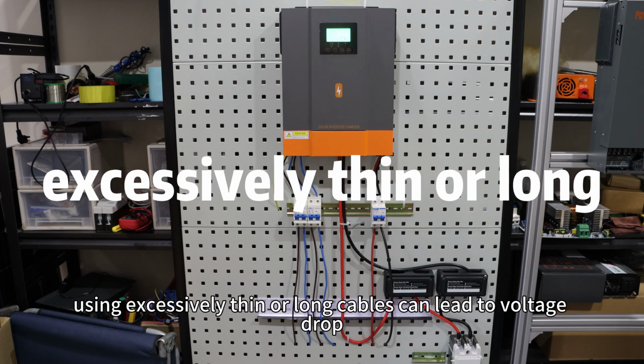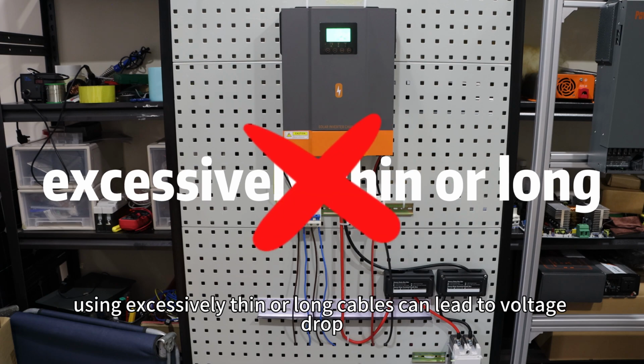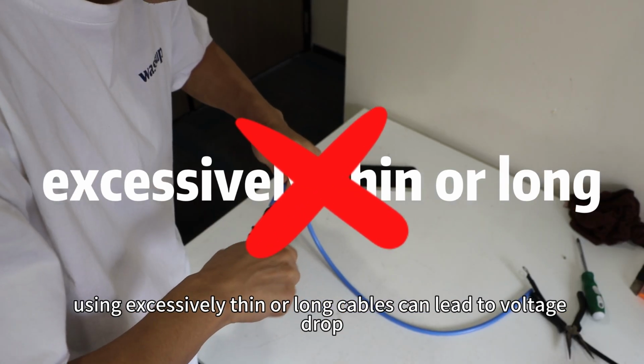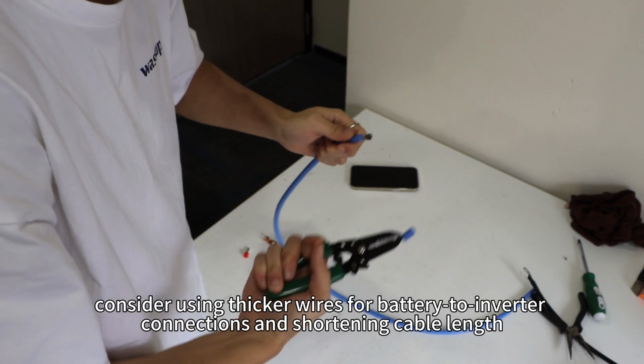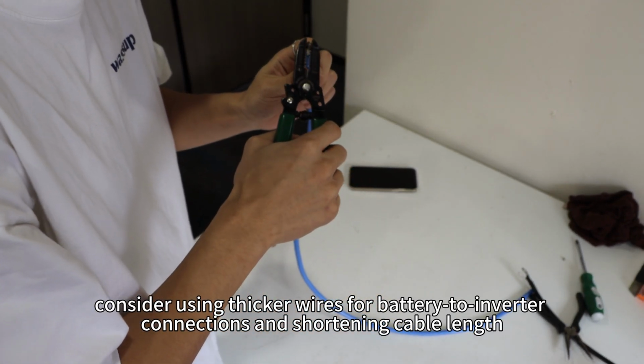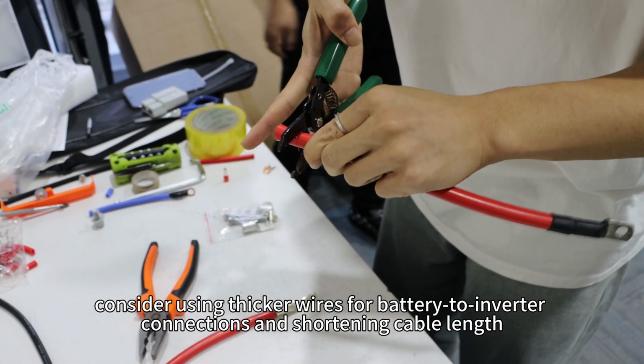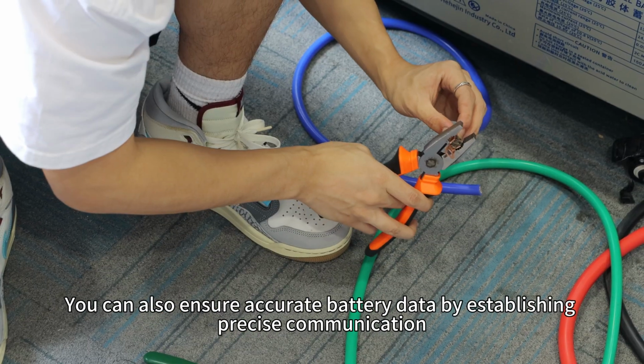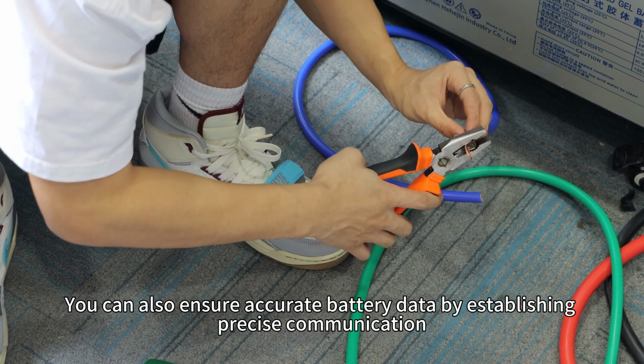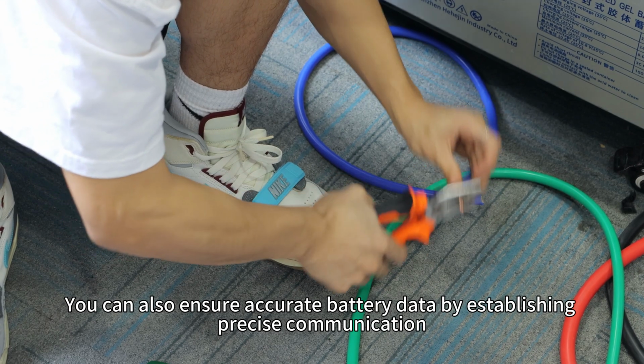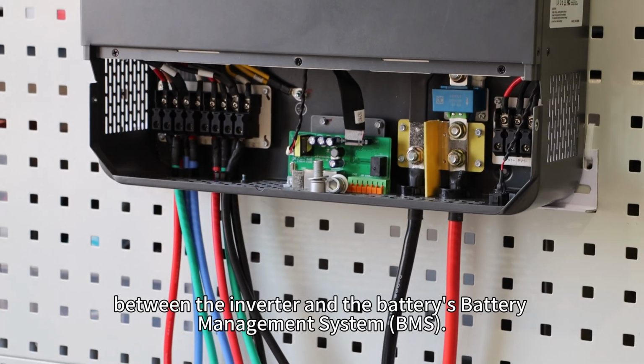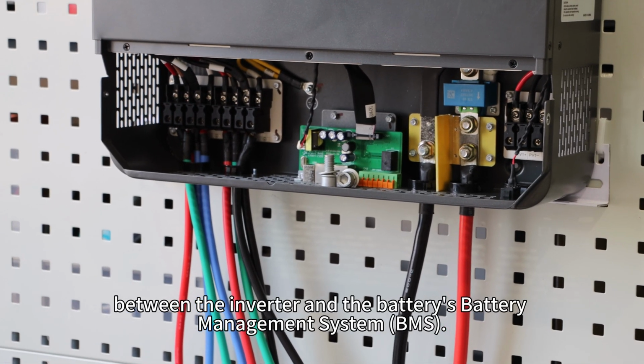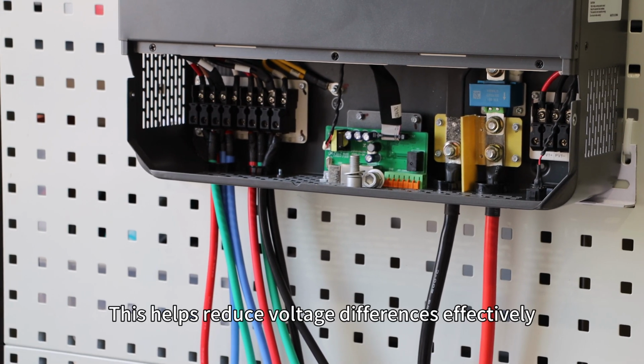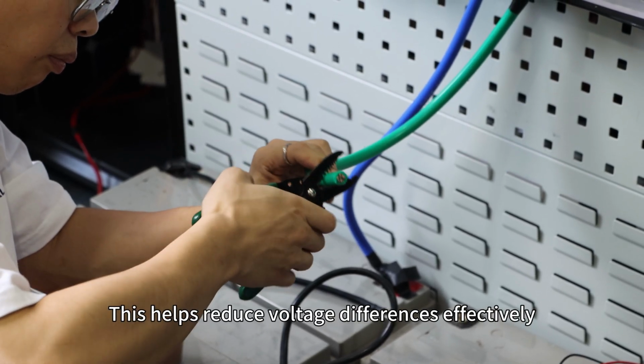Additionally, using excessively thin or long cables can lead to voltage drop. To address this, consider using thicker wires for battery to inverter connections and shortening the cable length. You can also ensure accurate battery data by establishing precise communication between the inverter and the battery's battery management system. This helps reduce the voltage difference effectively.